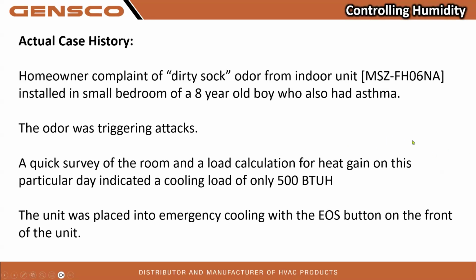And this is an actual case history to illustrate that point. I went out to a job site where a homeowner had a complaint of dirty sock odor from an indoor unit. It was an FH06, part of a 3C30 multi-zone system. The bedroom was occupied by an 8-year-old boy who had asthma, and the odor from his unit was triggering asthma attacks. I did a quick survey of the room based on its size and its exposure, and came up with a load calculation on that particular day of only 500 BTUs of cooling. I placed that unit in emergency cooling with its emergency operation push button on the front of the unit.